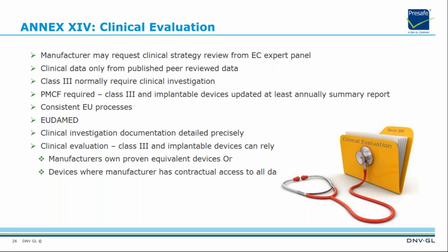For clinical evaluation, the manufacturer may request a clinical strategy review from an EC expert panel; clinical data only from published peer-reviewed data. Class 3 normally requires clinical investigation. Clinical investigation is a part of clinical evaluation for those medical devices which need to be investigated. Post-marketing clinical follow-up is required for Class 3 and implantable devices.